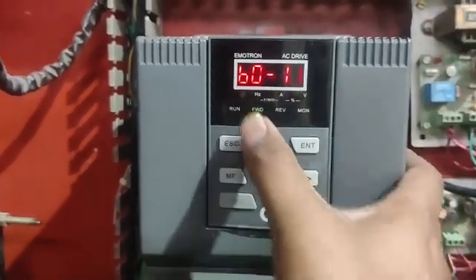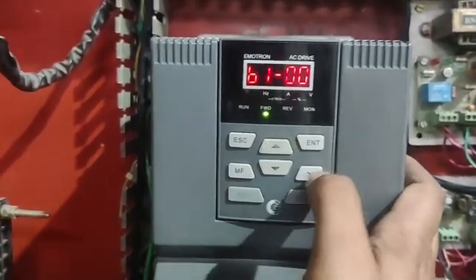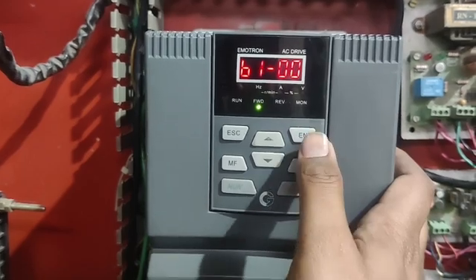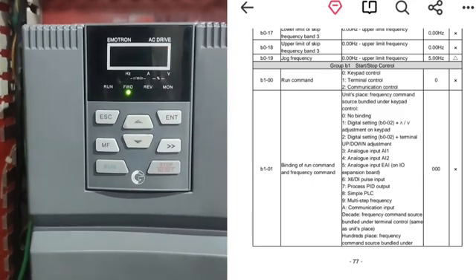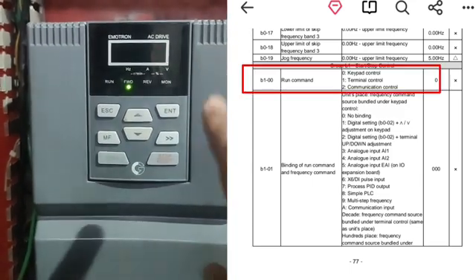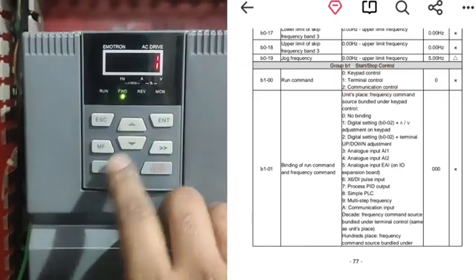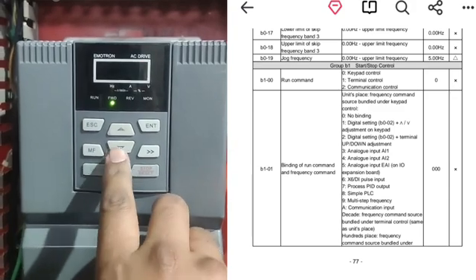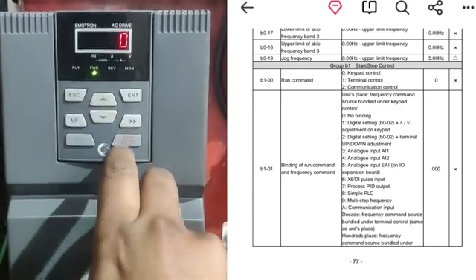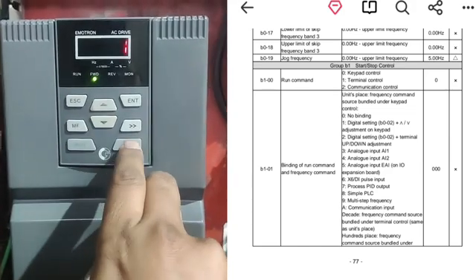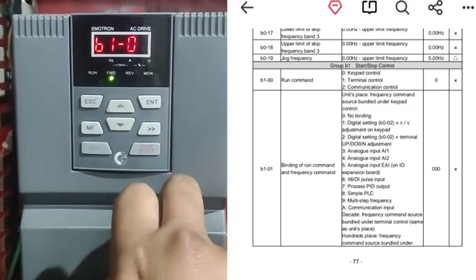Parameter B100 is Run Command — from where we can start and stop our drive. We set one: with value one we can start/stop the drive with a push button or selector switch. If you want to start/stop in local mode using the drive's Run and Stop keys, set zero. For now we set one for run command from an external push button.